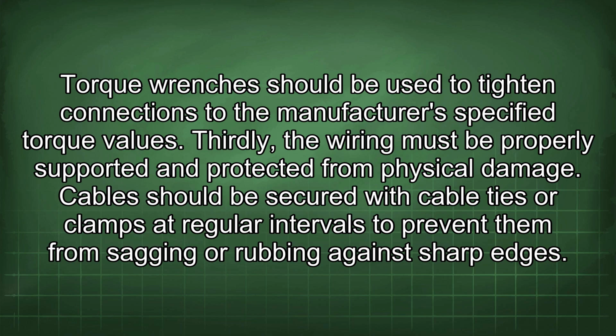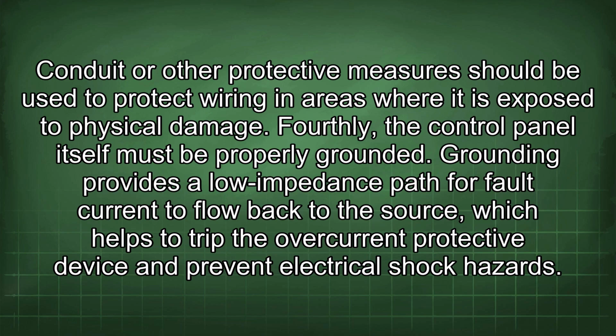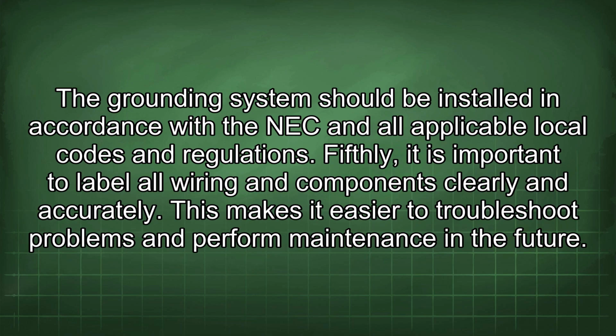Thirdly, the wiring must be properly supported and protected from physical damage. Cables should be secured with cable ties or clamps at regular intervals to prevent them from sagging or rubbing against sharp edges. Conduit or other protective measures should be used to protect wiring in areas where it is exposed to physical damage. Fourthly, the control panel itself must be properly grounded. Grounding provides a low impedance path for fault current to flow back to the source, which helps to trip the overcurrent protective device and prevent electrical shock hazards. The grounding system should be installed in accordance with the NEC and all applicable local codes and regulations.